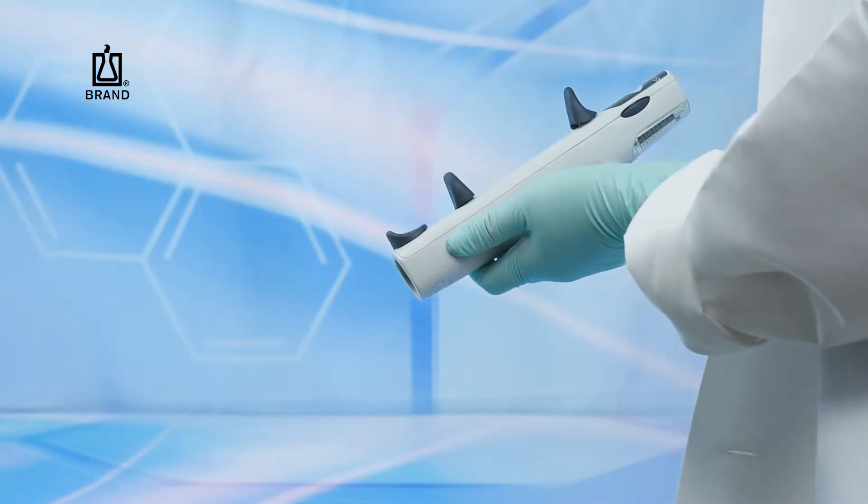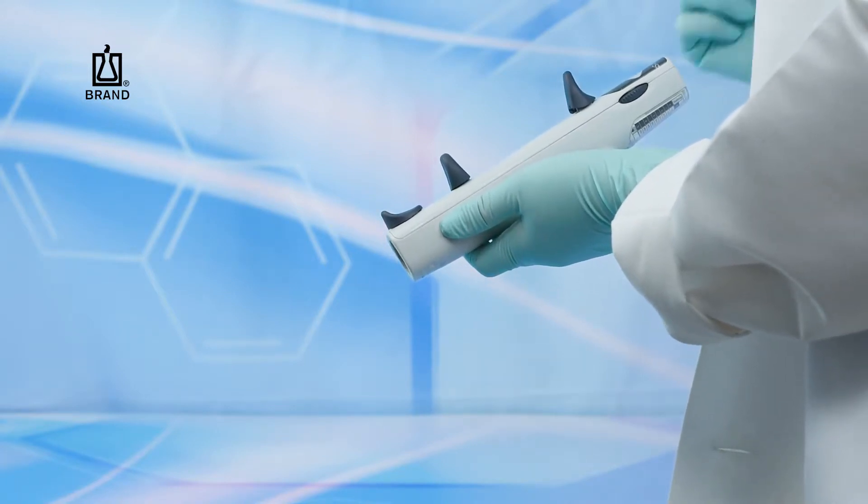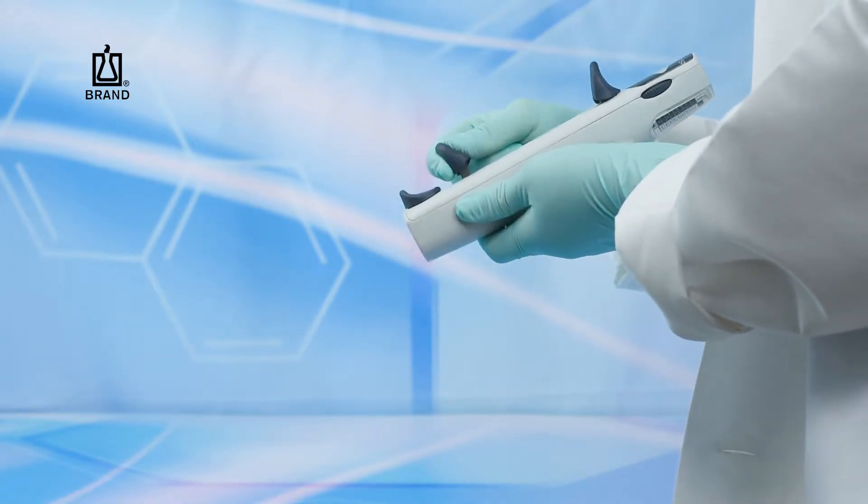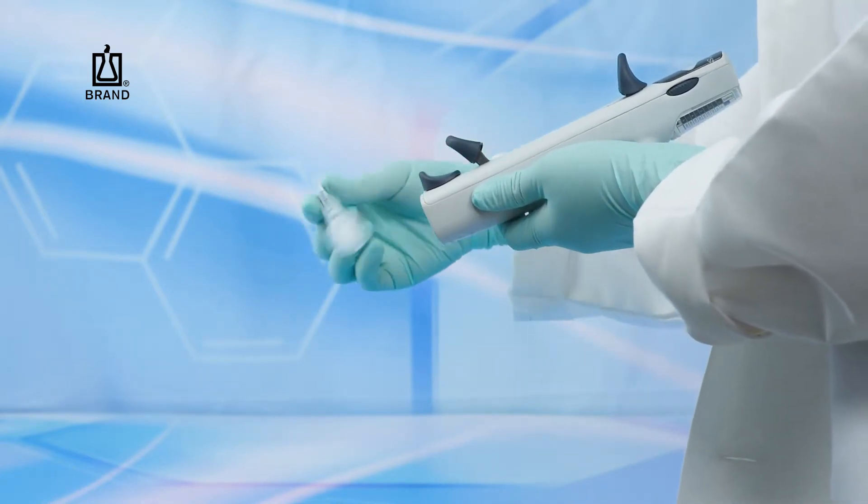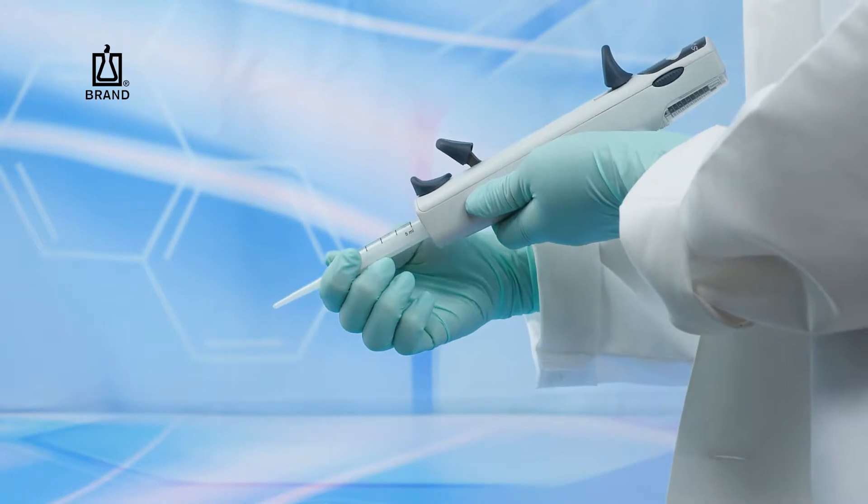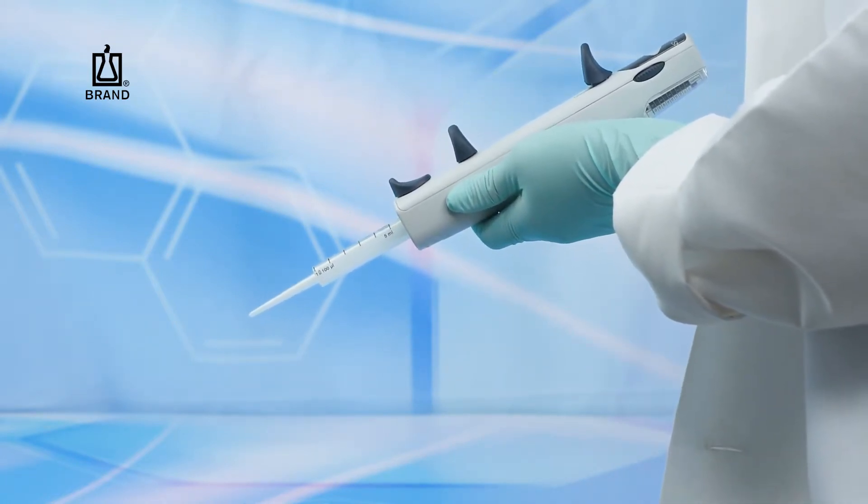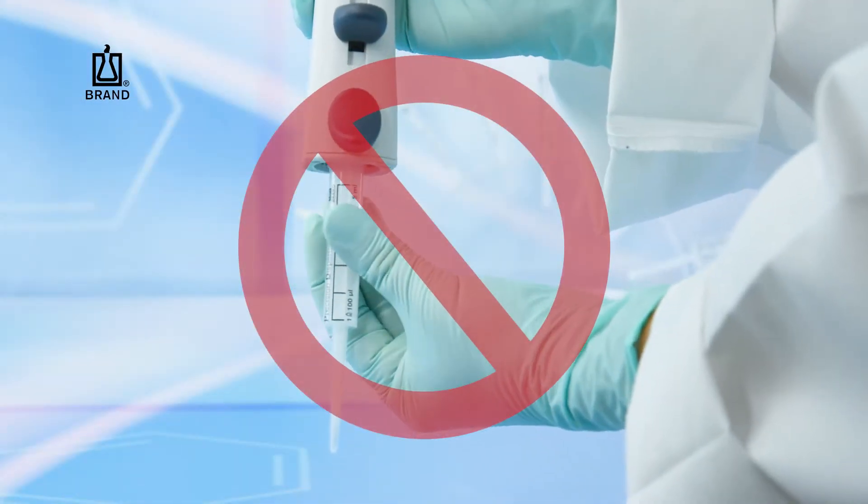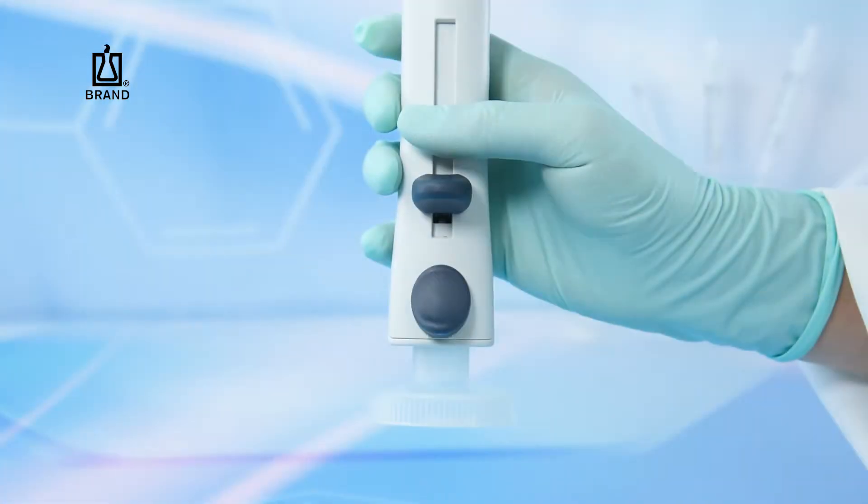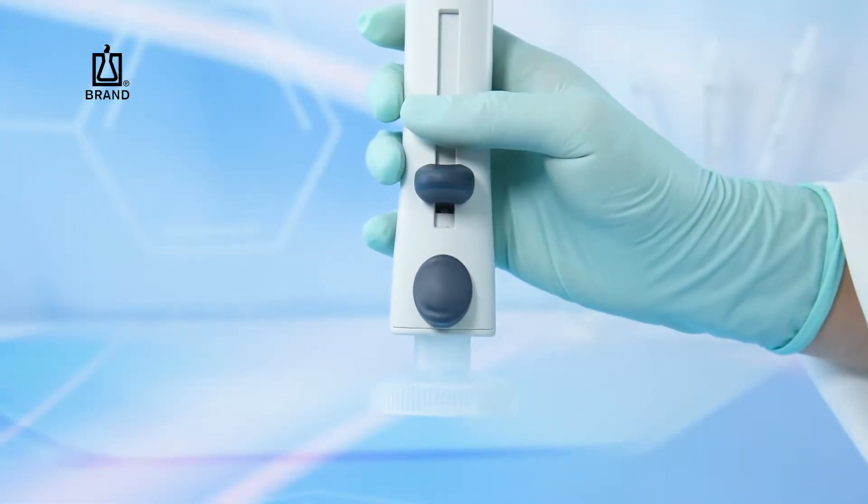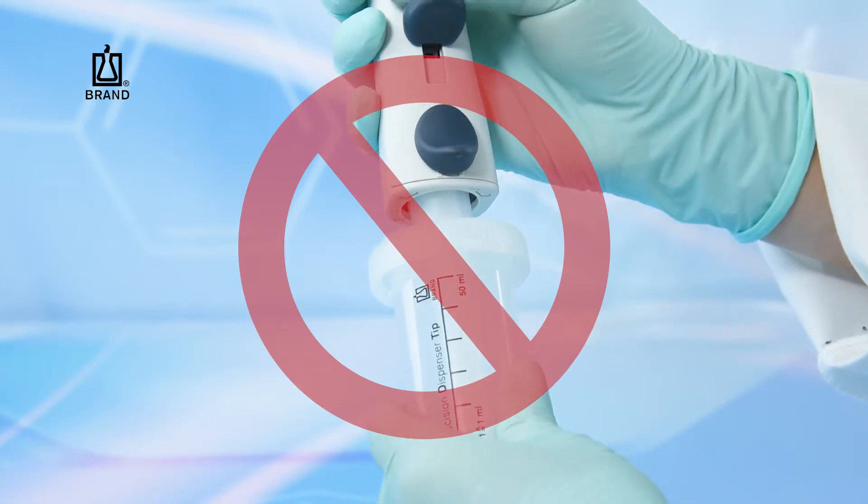To insert the selected PD tip into the HandyStep S, ensure that the locking filling lever is pushed to the lowermost unlocked position. Push the PD tip straight into the lower section of the HandyStep S, then swing the locking filling lever into place to lock the piston into the unit. Do not twist the tip after inserting. Never try to insert a 25 mil or 50 mil PD tip into the HandyStep S with the adapter already inserted into the instrument.